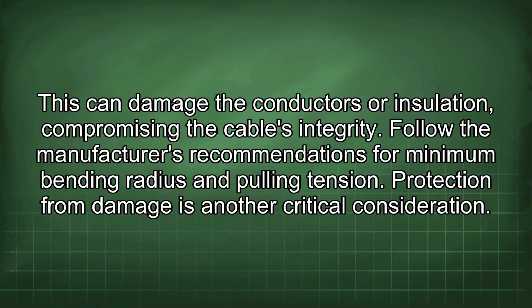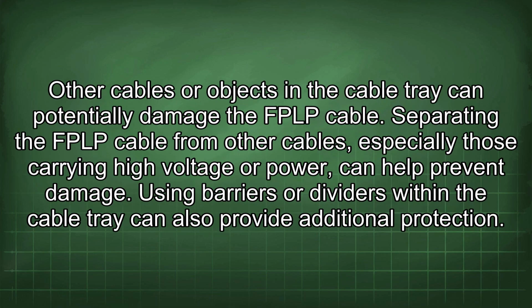Protection from damage is another critical consideration. Other cables or objects in the cable tray can potentially damage the FPLP cable. Separating the FPLP cable from other cables, especially those carrying high voltage or power, can help prevent damage. Using barriers or dividers within the cable tray can also provide additional protection.